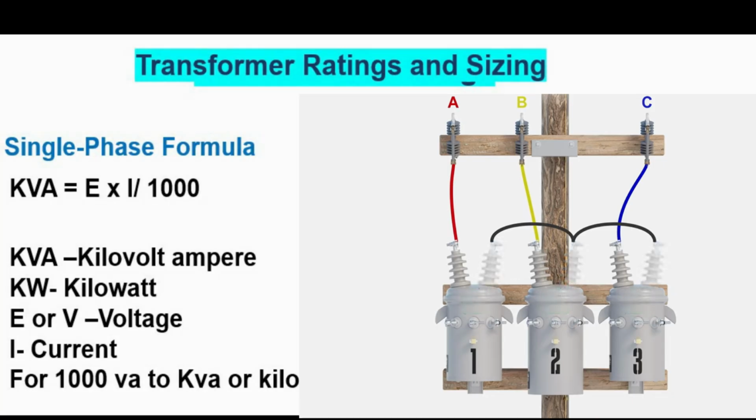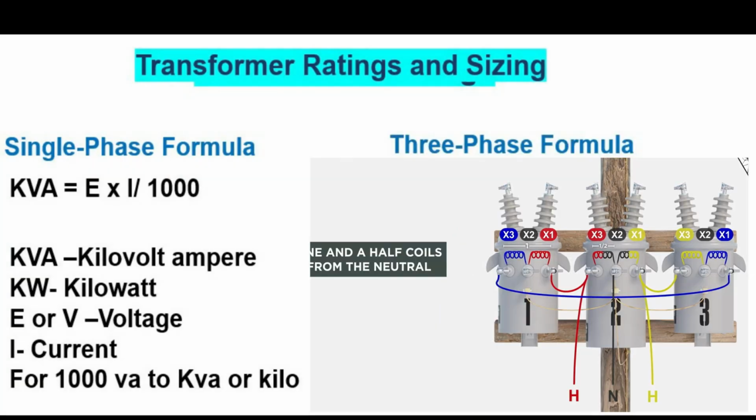select and size transformers. The formula for finding the required kVA or transformer size for single-phase power is the following. Companies or businesses that require three-phase power need to add an extra component in the formula to arrive at the correct transformer size, for example, the square root of 3, or 1.732. This figure is a constant found in three-phase, as the phases do not generate the same amount of power simultaneously.